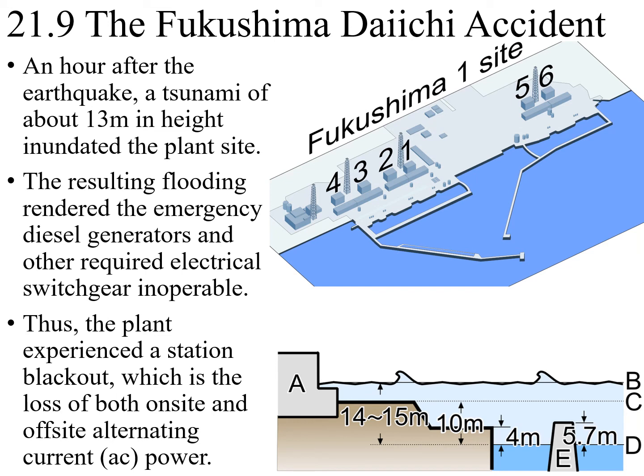On March 11, 2011, a multi-unit accident occurred at the Fukushima Daiichi plant on the northeastern coastline of Japan. In the afternoon, an earthquake, a seismic event registering 9.0 on the scale, struck 70 kilometers off the east coast, resulting in an automatic shutdown of reactor units 1, 2, and 3, which were operating at rated power at that time. Units 4, 5, 6 were shut down for refueling. The earthquake caused damage to the nearby electric power system, resulting in the loss of offsite power. But the on-site diesel generators were started to supply equipment such as the decay heat removal system for these 3 boiling water reactors, which began operation in the 1970s.